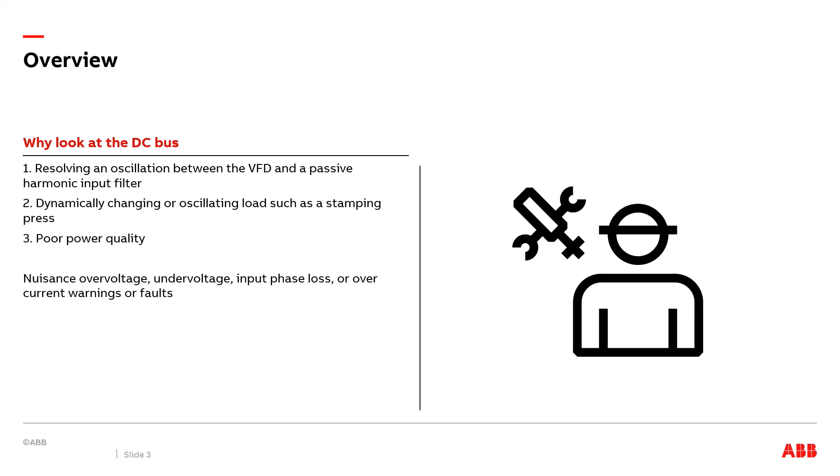Here are three reasons why you may need to use an oscilloscope to look at a VFD's DC bus. The first one is if a VFD has been packaged with a passive harmonic input filter. There could be oscillations between the drive and the filter. The second one is in industrial applications sometimes there are oscillating loads such as stamp presses that can cause ripples on the DC bus. And the third cause could be poor input power quality to the VFD that could be causing issues on the drive's DC bus. All these issues could cause the drive to trip out on nuisance over voltage, under voltage, input phase loss, or over current warnings or faults.